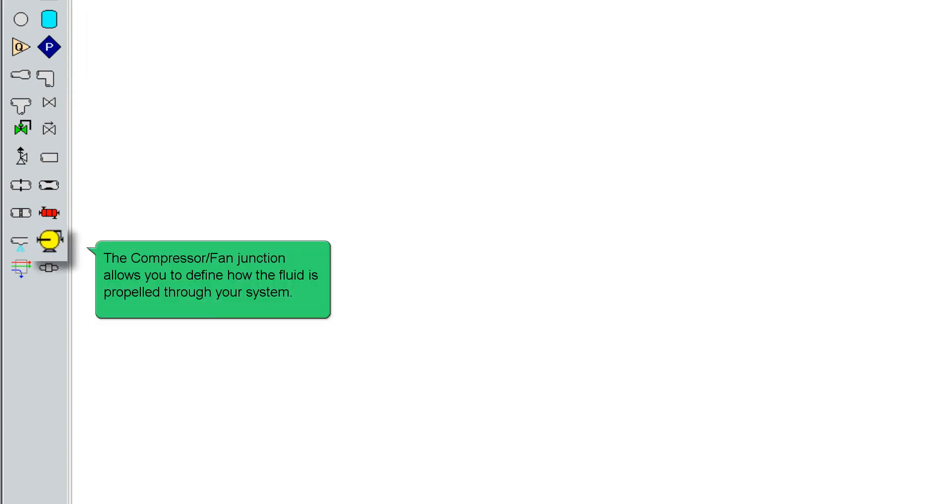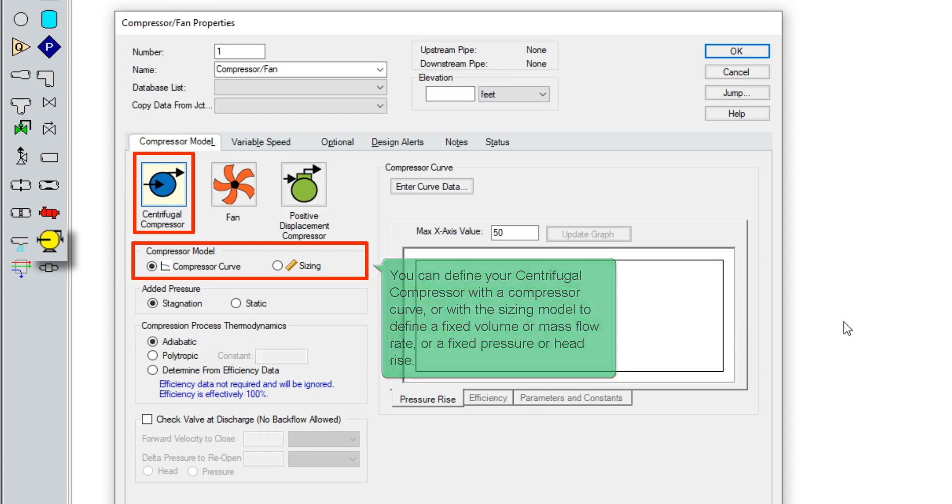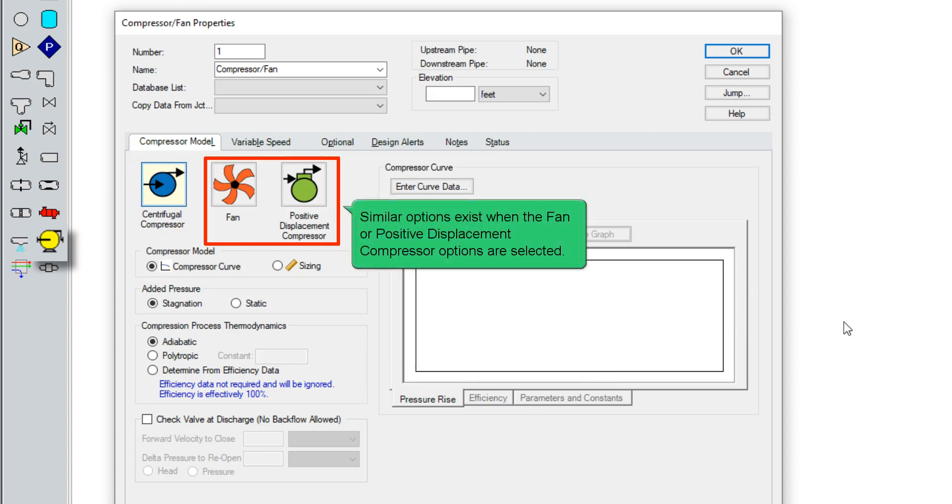The compressor junction allows you to define how the fluid is propelled through your system. You can define your centrifugal compressor with the compressor curve, or with the sizing model to define a fixed volume or mass flow rate, or a fixed pressure or head rise. Similar options exist when the fan or positive displacement compressor options are selected.